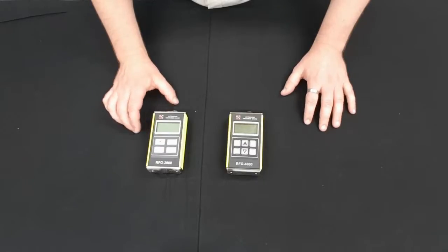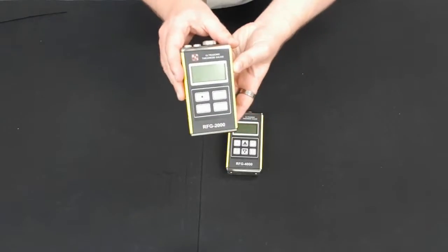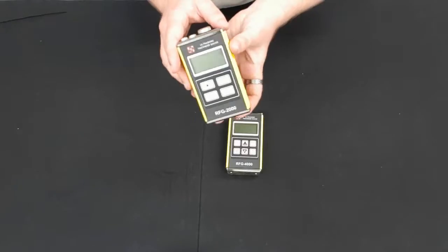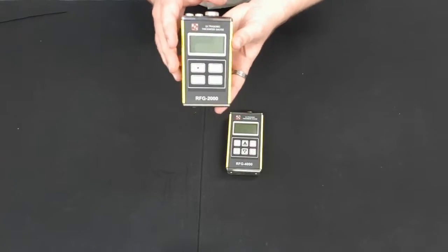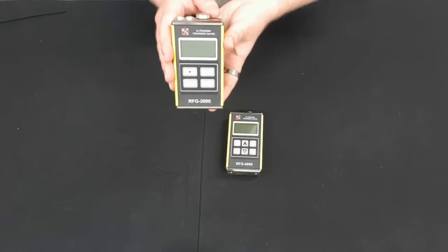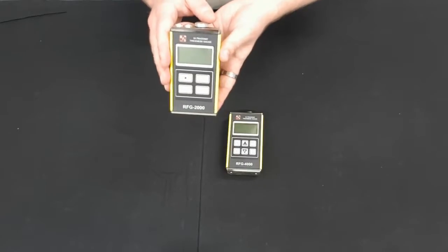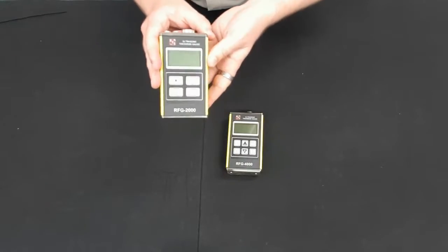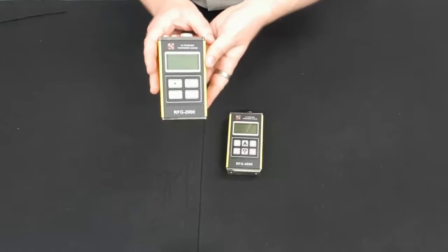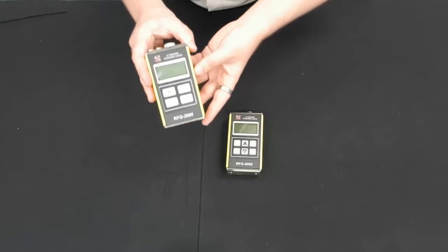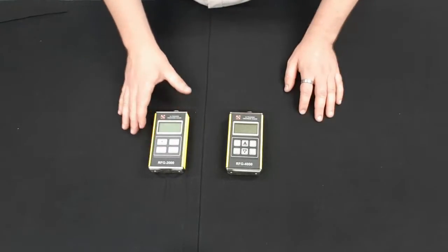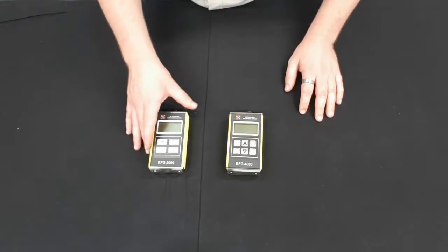So we also have some other options. Here we have the RFG 2000. Now this is very similar to the 4000, however it has a preset velocity. So it's locked to carbon steel at 5,920 meters per second. Now this means it can only be used on carbon steel, but it makes it very, very simple to use. There's a lot less settings involved. If you have someone that doesn't really deal with thickness gauges a lot, and they're only measuring steel, this is ideal for what you want.